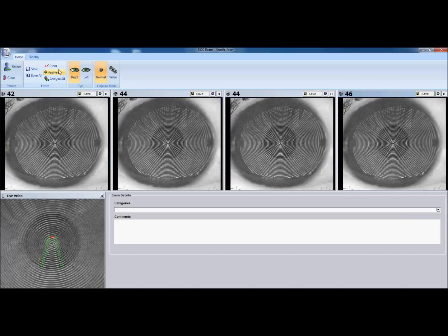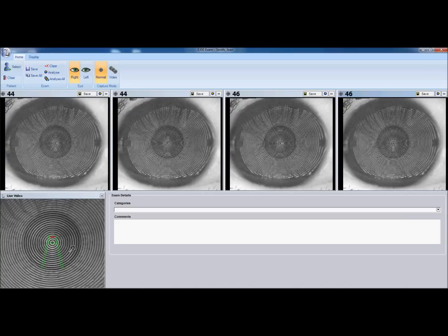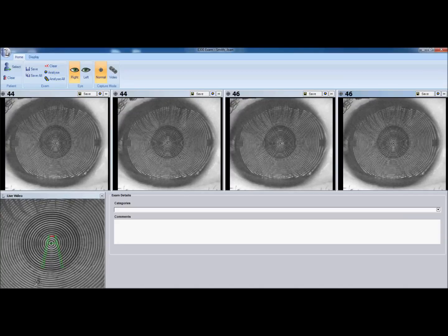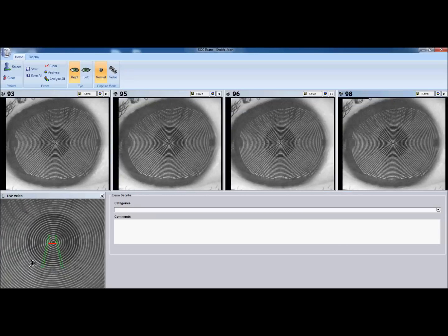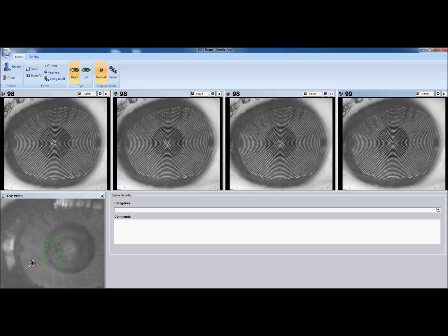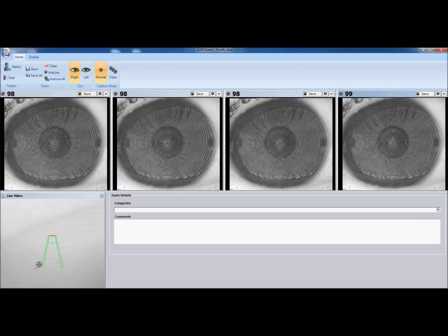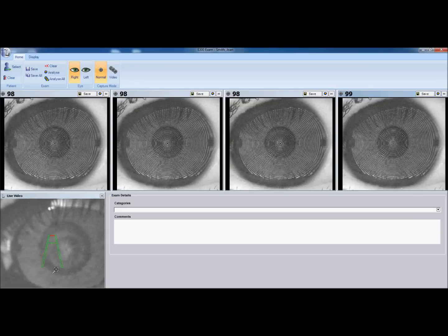Let's again focus in on that video image. We'll put the instrument near into position with the green crosshair. You can see there's a little bit of tear film breakup at various points. We'll ask our patient to blink to smooth that out. When it's smooth, you can go in and take your capture. This concludes the section on capturing with your Medmont E300 corneal topographer.